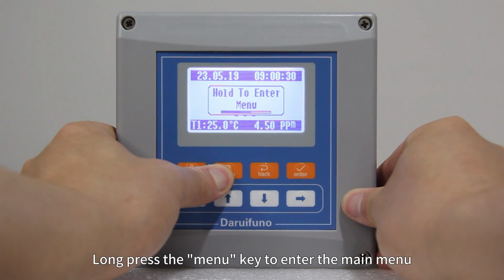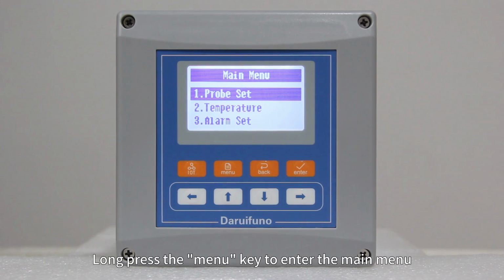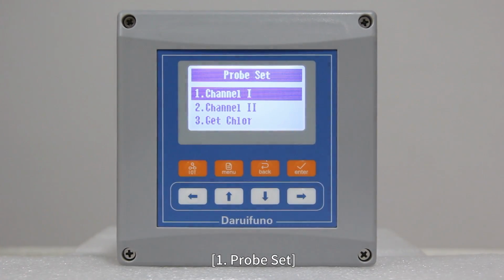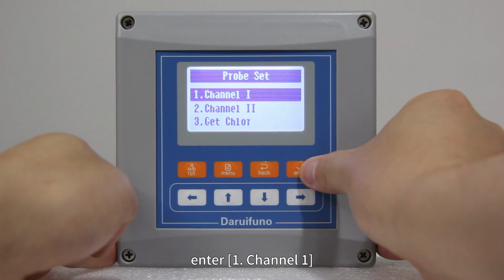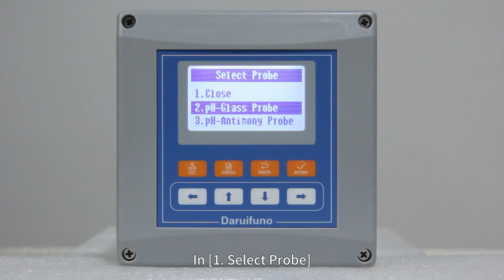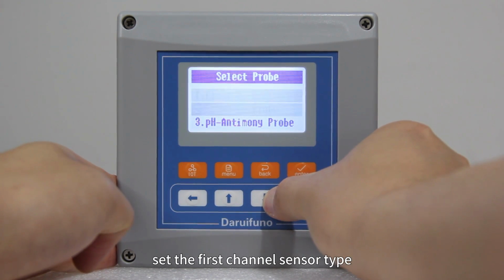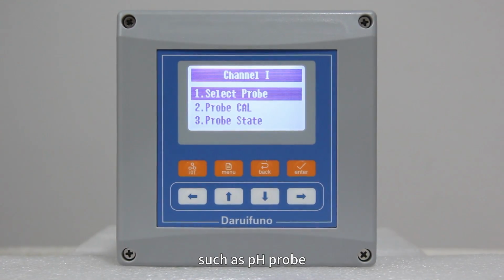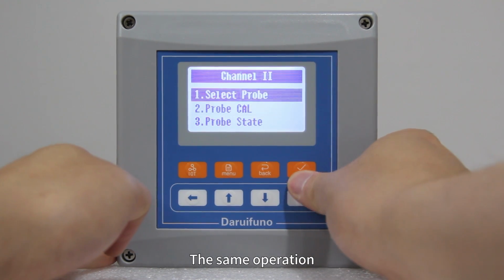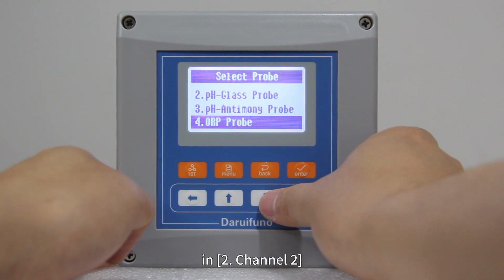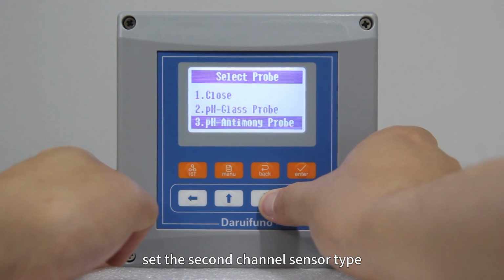Long press the menu key to enter the main menu. After selecting 1. Probe Set, enter 1. Channel 1. In 1. Select Probe, Set the first channel sensor type, such as pH probe. The same operation. In 2. Channel 2, set the second channel sensor type, such as ORP probe.